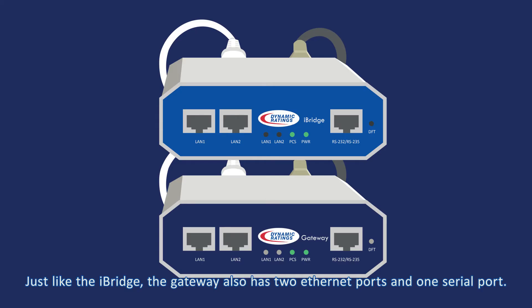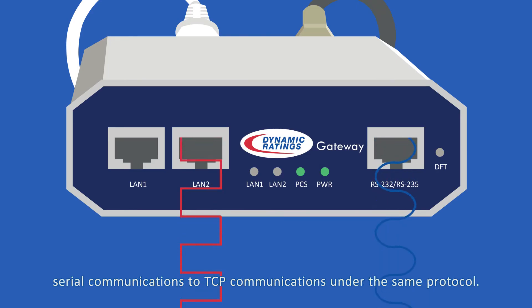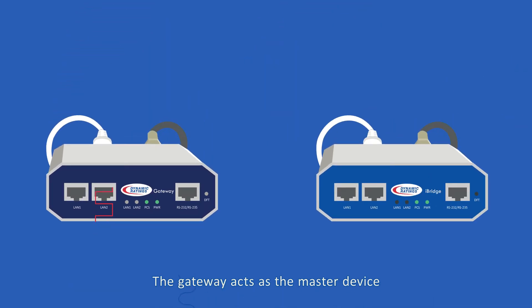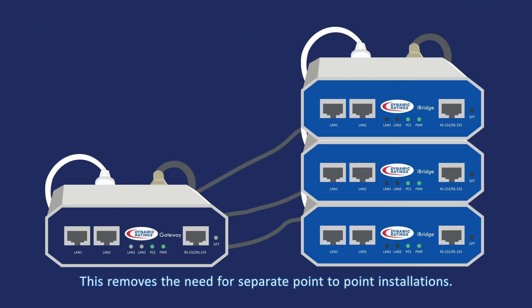Just like the iBridge, the gateway also has two Ethernet ports and one serial port. Pairing a gateway with an iBridge can also convert serial communications to TCP communications under the same protocol. The gateway acts as the master device and can communicate with a large amount of iBridge units, removing the need for separate point-to-point installations.